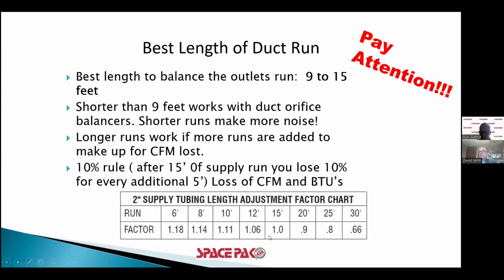So, 15 feet long. This includes the 3 feet of sound attenuator, which is on the end of every run. So you cut an additional 12 feet, you'd put the fittings on that, and you'd have a 15 feet total run, including the sound attenuator. That's a factor of 1.0. That's one fully opened outlet. If you have 20 feet in length, including the sound attenuator, you lose that 10% for that extra 5 feet. You only have 0.9 of an outlet. At 25, you've got 0.8 of an outlet. At 30, you've got 0.66.